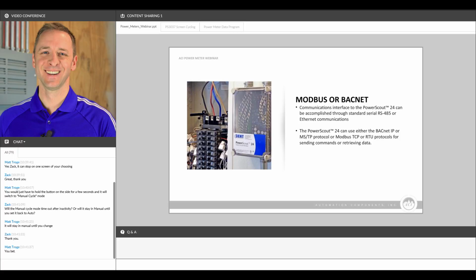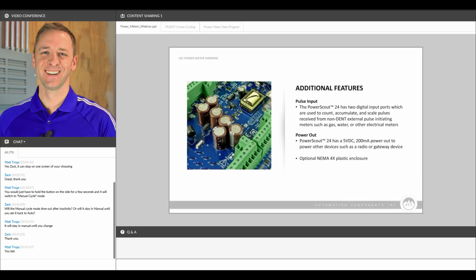But there are a couple of unique features on the PS24 that aren't available with the 3037, and those are that the PS24 has 2 digital input ports, so it can accept pulse inputs from external devices such as gas meters, water meters, or any other types of devices that are outputting a pulse signal.